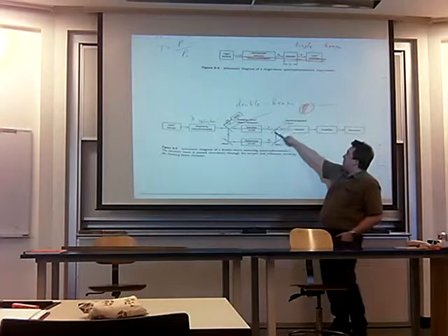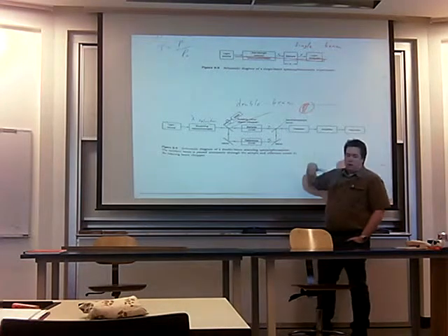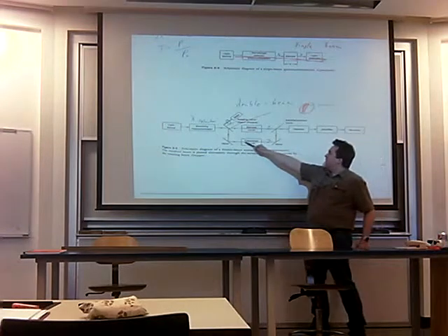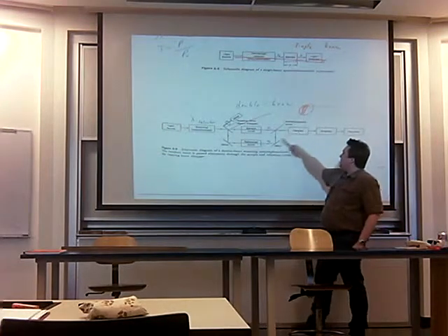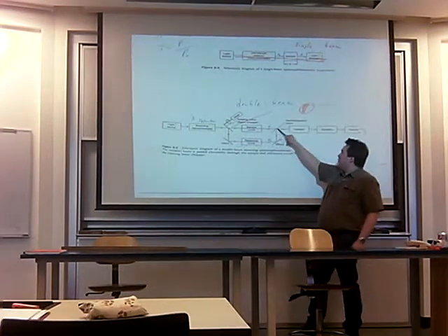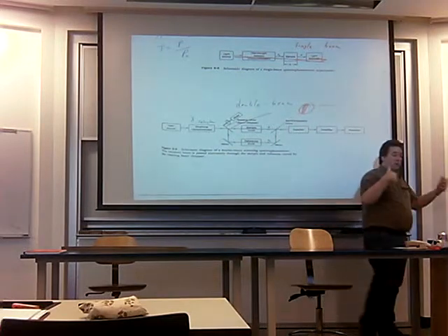We then have a semi-transparent mirror, basically a little one-way glass, so that the light that comes from the reference gets sent to the detector, and the light that comes from the sample gets sent to the detector. So the detector is now alternatingly seeing blank or reference, sample, reference, sample.